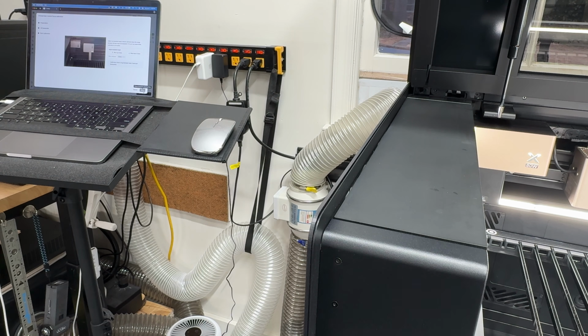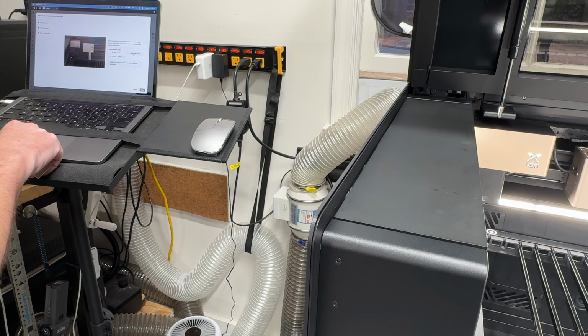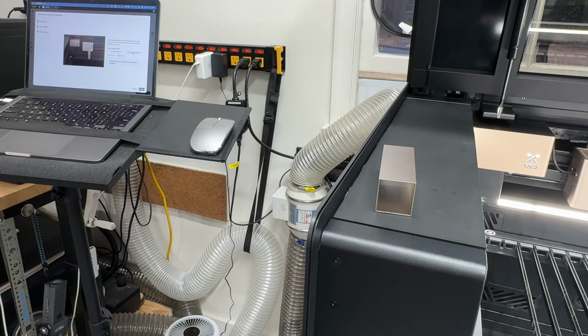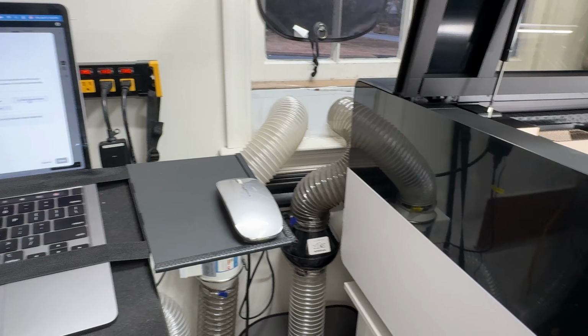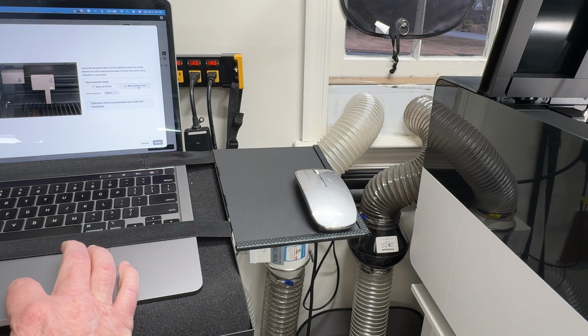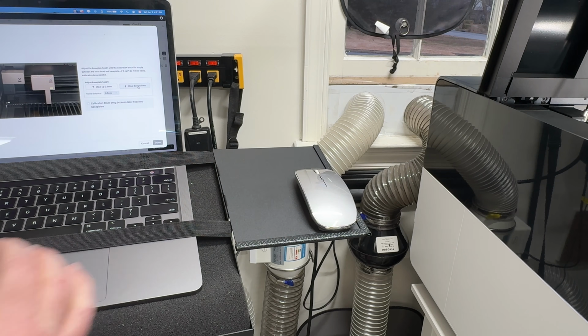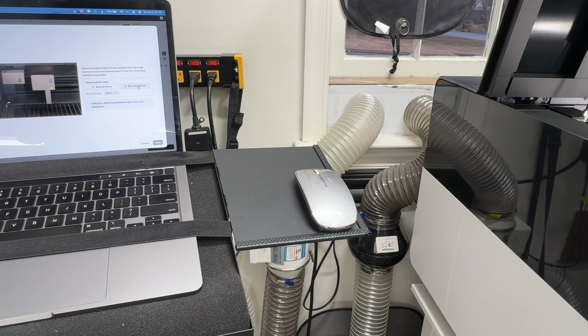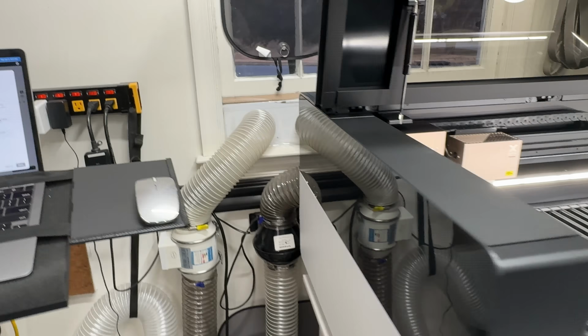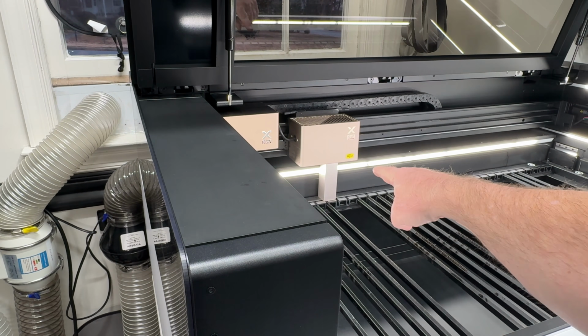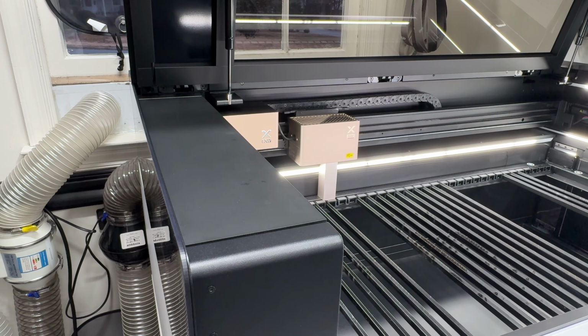Okay, now we're going to take our calibration unit and we're going to adjust the base plate till it's snug. And we're going to do that by putting this under here. And I can't fit mine in, so we're gonna have to lower ours down. And we can do this by clicking on the screen over here. I wanna show you. We're kind of got two things going on at the same time. So I'm clicking this down for mine. And it's moving in little 5mm increments so that I can get this plate under my laser module. So now you can see I can fit that under there now. So now I'm going to raise it up.